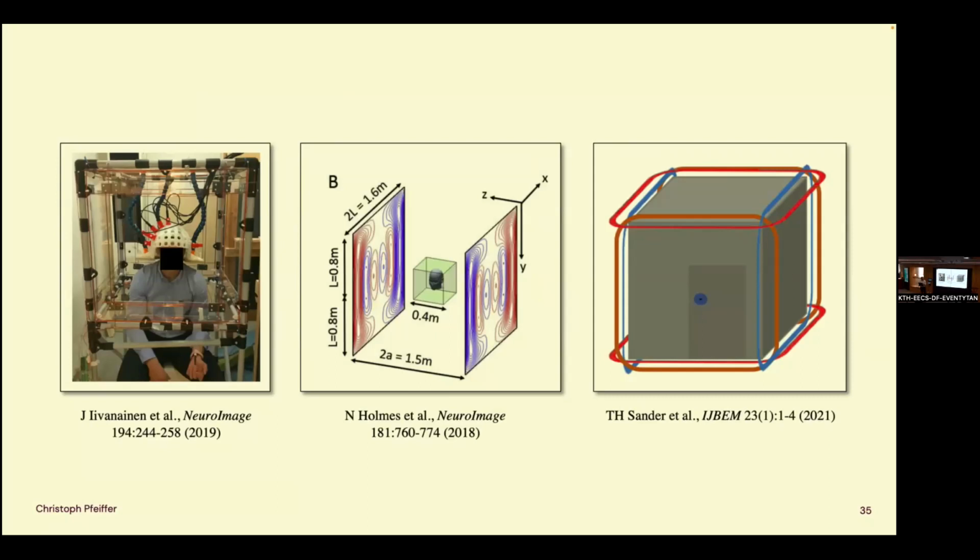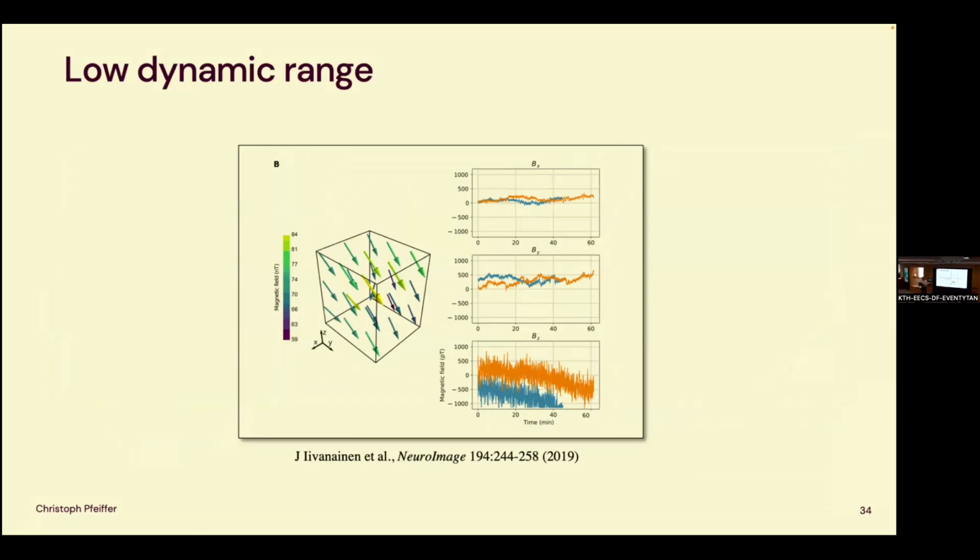Sounds very simple, but of course this is quite complex. You can see here this type of coils. They're very complicated to design and construct. And because of these fluctuations that you can observe in a room, ideally you also want dynamic nulling. So not just turn it on once, calibrate it, and it's good, but you keep measuring the signal and cancelling it.